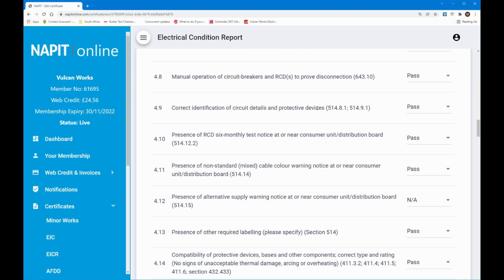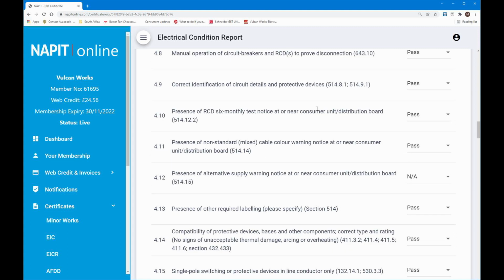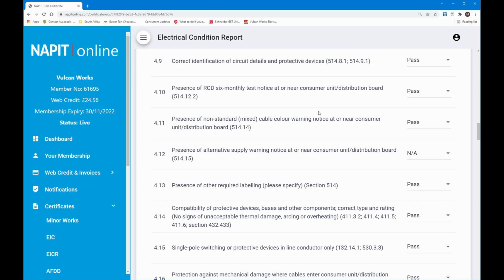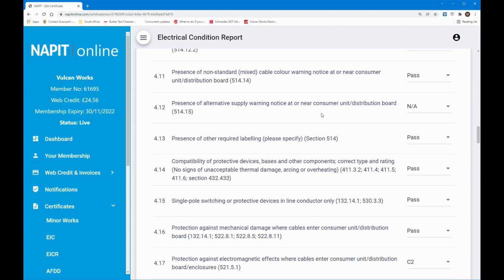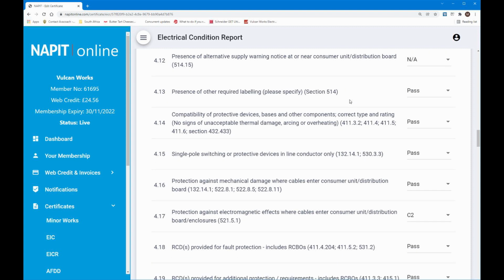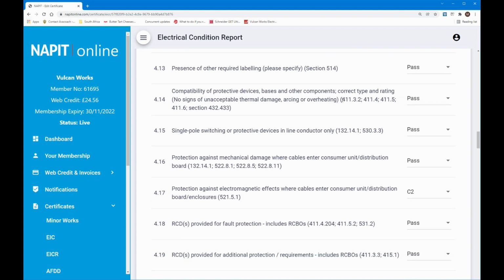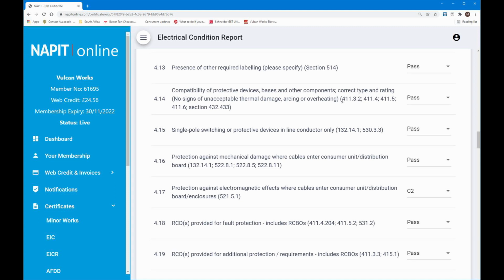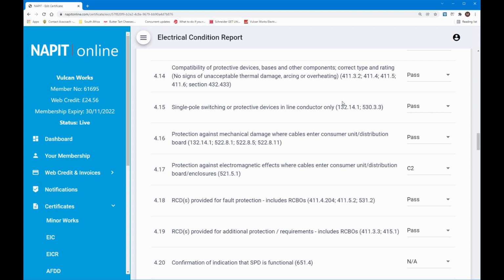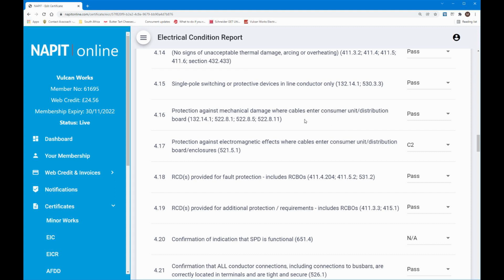Correct identification for the circuit details, they are now. Presence of an RCD six monthly test notice, yes, because I put it on. Non-standard mixed cable warnings, yes, because again I put that on. Presence of an alternative supply warning, there isn't one, so that's not applicable. Presence of other required labelling, yes, there is. Compatibility of protective devices, bases and other components, correct type and rating. No signs of unacceptable thermal damage, arcing and overheating, that's fine. Single pole switching or protective devices in line conductors, that's fine. And protection against mechanical damage is fine.